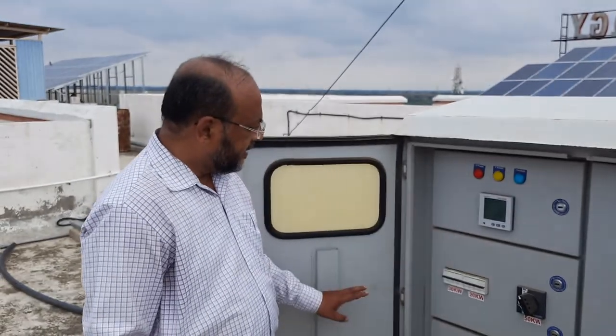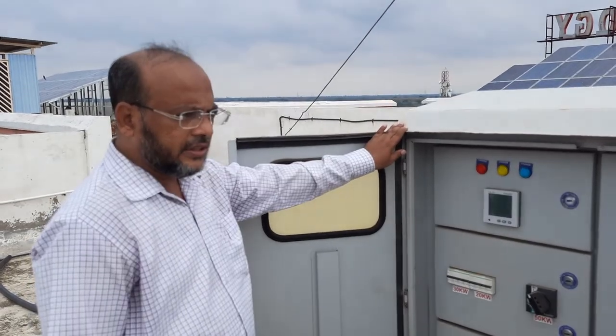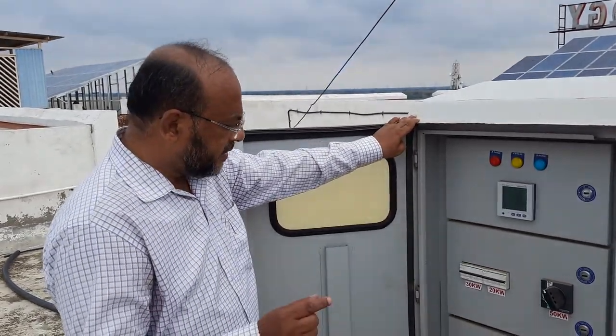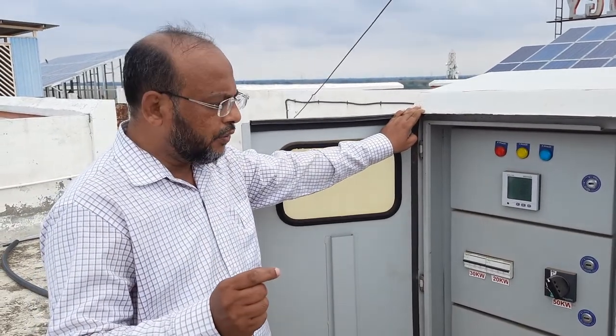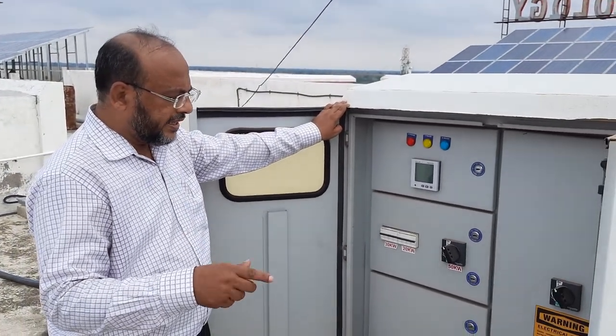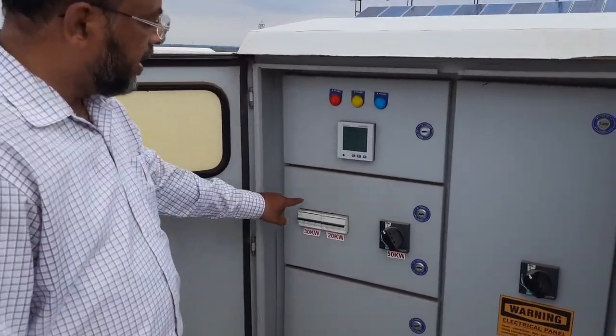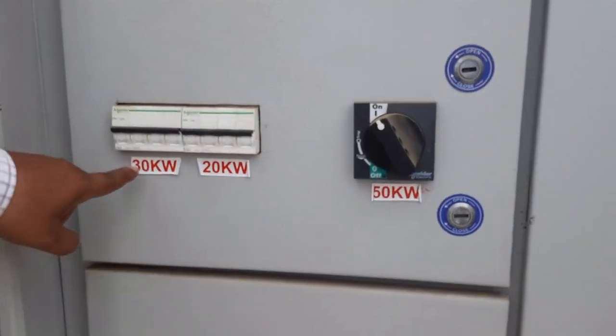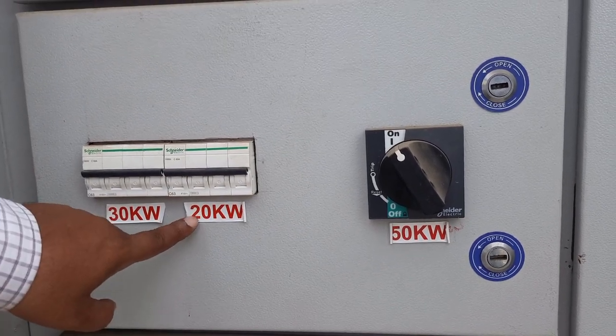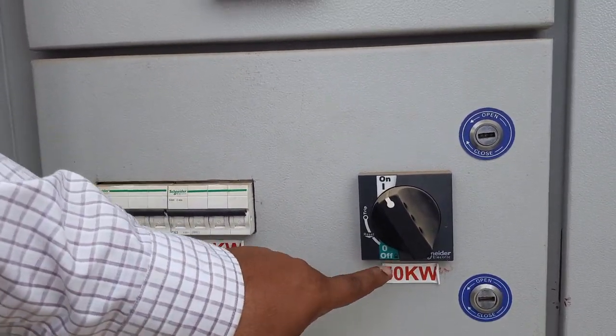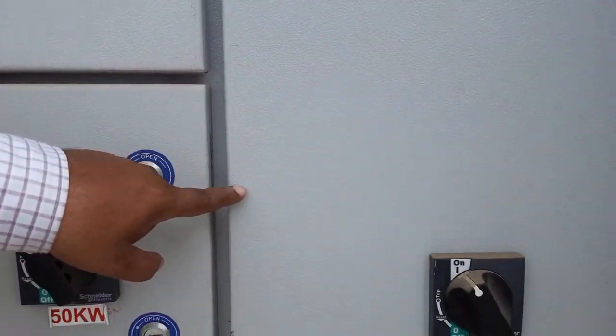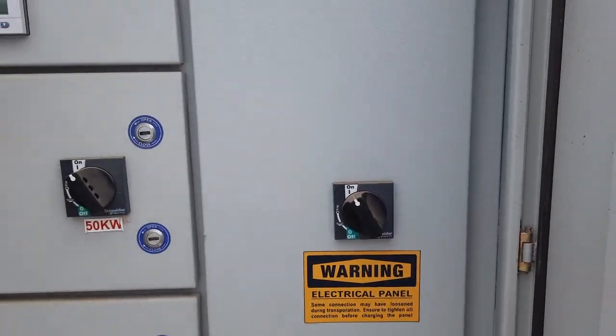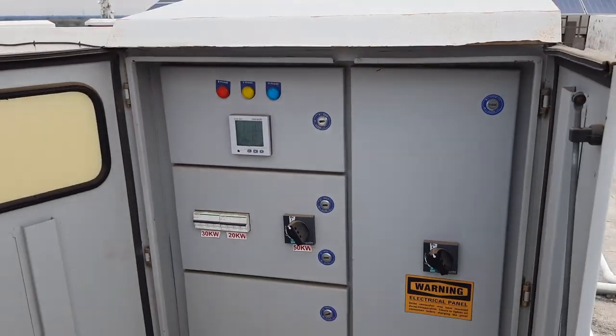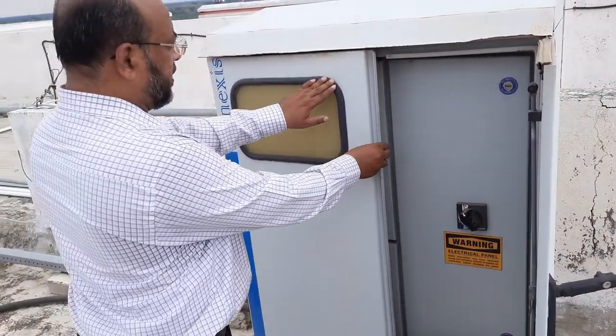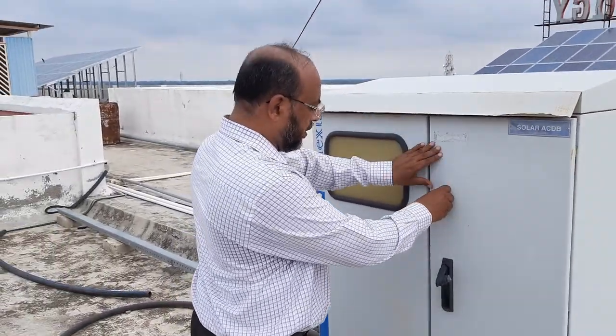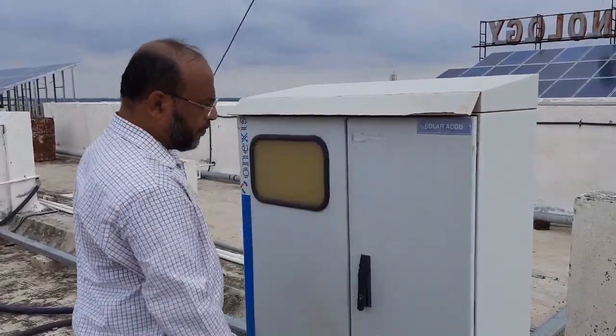This is the ACDB. In the 100 kilowatt solar plant there are 3 inverters: 50 kilowatt, 20 kilowatt and 30 kilowatt. The inverter output, that is the AC supply, is connected into the ACDB. So this is the 30 kilowatt inverter switch, 20 kilowatt inverter switch and 50 kilowatt. It is combined with the main switch of 150 ampere, and now it is connected to the substation. It is an outdoor type canopy, IP65, a drip proof panel used for outdoor purposes.